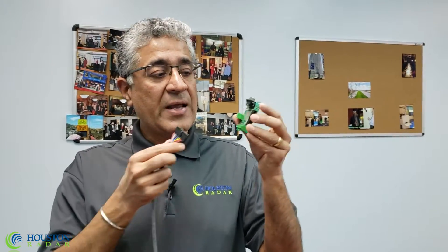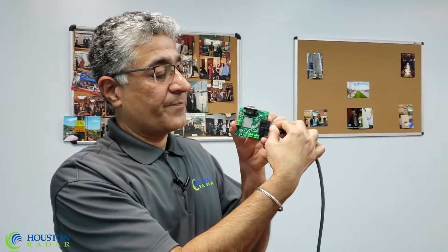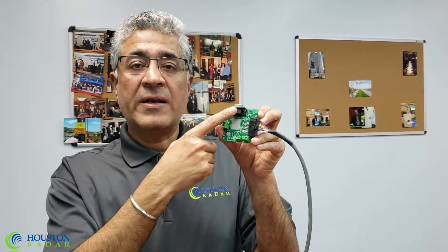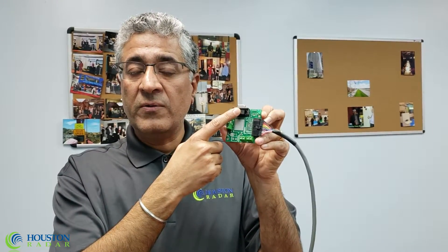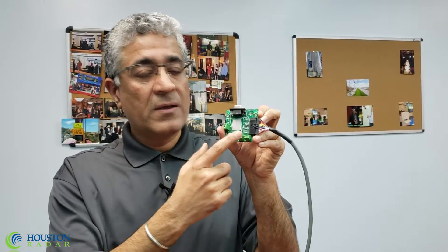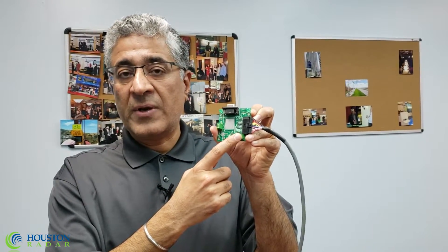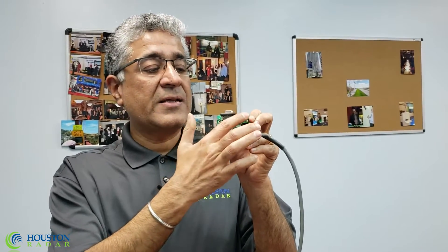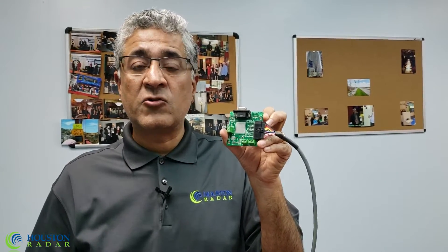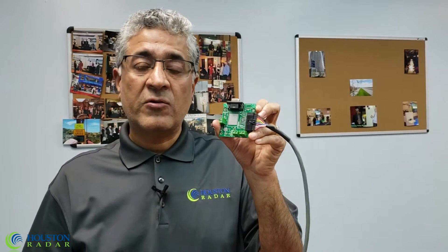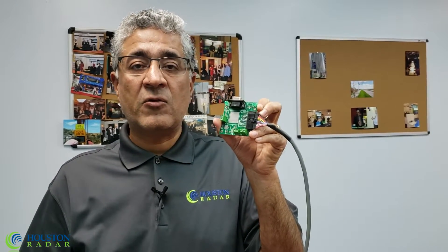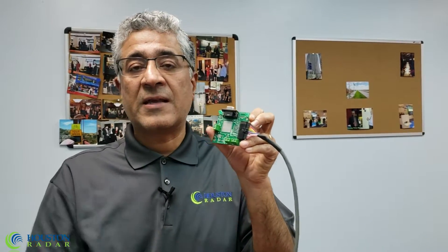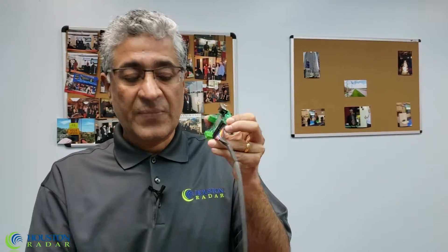This simple I.O. connector board breaks the Molex connector out into a DB9 for RS-232, either to a PC connection or a Bluetooth dongle, power screw terminals, trigger output screw terminals, as well as gives you two indicator lights that two out of your six trigger outputs have been activated. If you need to use more than two trigger outputs, then you would make yourself a different breakout board or break this cable out right here at this connector.